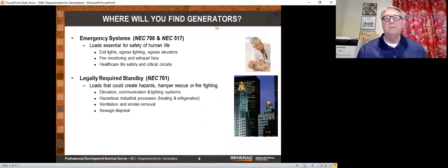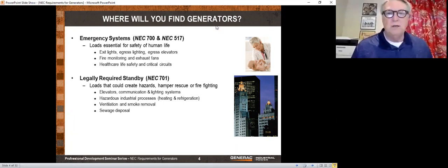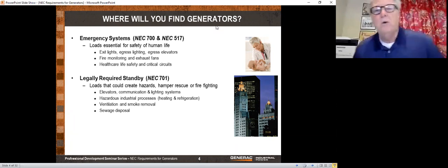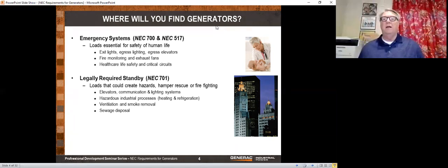So what are some examples of that? Exit lights, egress lighting, egress elevators, fire monitoring and exhaust fans. As you know, the National Electrical Code is published by the National Fire Protection Association, and fire is always near and dear to their hearts. So if you need that generator to get out of the building safely, then that becomes an emergency generator.